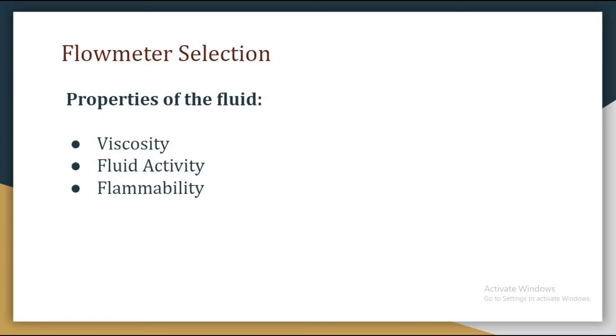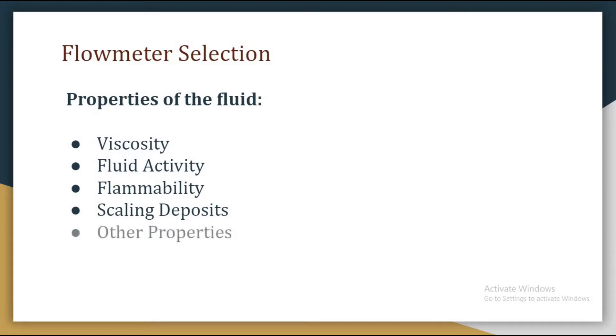We need to keep fluid reactivity in mind. We also need to be familiar with flammability — fluids which are inflammable require flow meters like the vortex flow meter, which are suitable for application in hazardous areas. Special care should be taken for fluids having a tendency to deposit scales, since scaling can block pressure lines and ducts. Other properties like compressibility, abrasiveness, transparency, electrical conductivity, magnetic properties, and lubricity should also be considered while selecting a flow meter.